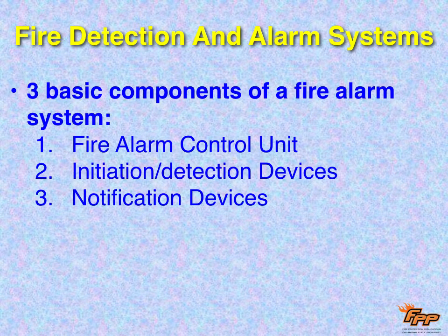So again, let's get back to alarm systems. There are three basic components of a fire alarm system: the FACU, or Fire Alarm Control Unit, sometimes called the Fire Alarm Control Panel, or FACP; the initiation or detection devices; and the notification devices. And this is like our human fire watch. The fire alarm control unit is like his brains. The initiation detection devices are like his or her senses: the nose, the eyes, the hearing, the sense that we get, oh, something's wrong, there's a fire. And then the notification devices are like that bell or rattle or shouting out fire. This system is replacing a human fire watch and is actually quite a bit more effective and efficient.